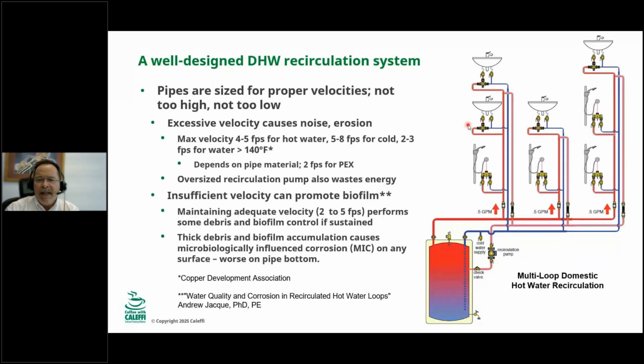In fact, I took a tech call this morning and it was about the size of the pipe. If you downsize to a 3/8 inch for your run out, you can have a longer run out. And I guess that has to do with the volume of water that's in that run out, right? The smaller pipe will have less water in it, so you'll get the hot water faster.